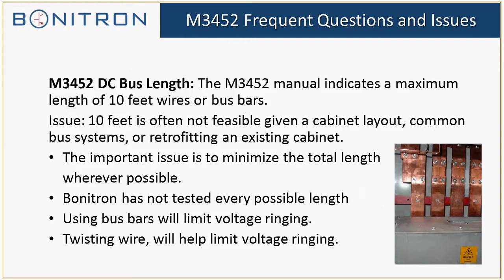However, it's often not possible for the customer to limit it to just 10 feet. Cabinets are laid out very differently from location to location. Common bus systems often have very long DC bus lengths, because you're trying to link several drives and several braking systems together. So often those are well over 10 feet. Likewise, if you're retrofitting an existing cabinet by mounting a 3452 on a wall next to the cabinet, it's really hard to get that DC bus length.